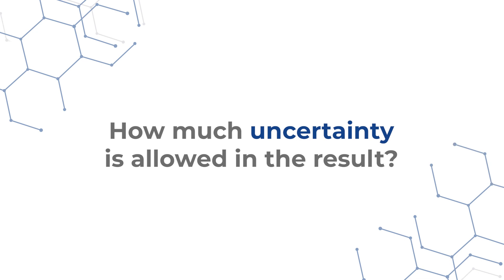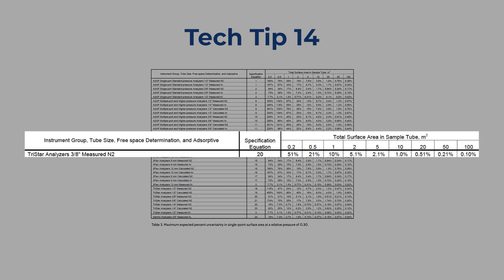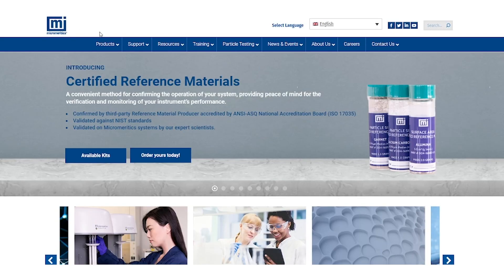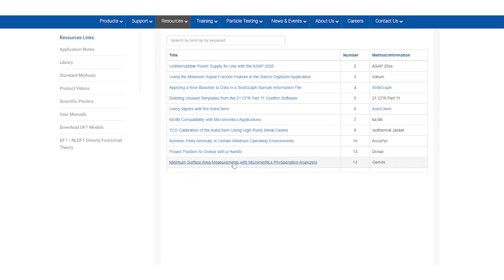Lastly, how much uncertainty is allowed in the result? This table found on TechTip 14 from Micromeritics shows the minimum surface area needed in square meters with the maximum percent uncertainty. For example, if the sample with one square meter total surface area was analyzed on the TriStar 3000 Plus with nitrogen on a three-eighths inch opening diameter tube with free space measured, then the maximum uncertainty of the data is 10 percent. For more details on uncertainty allowance, please visit the Micromeritics website and look over the TechTip 14.